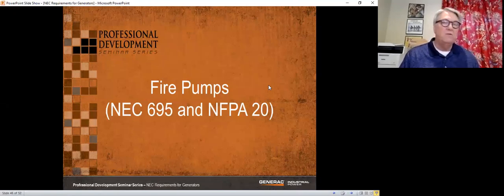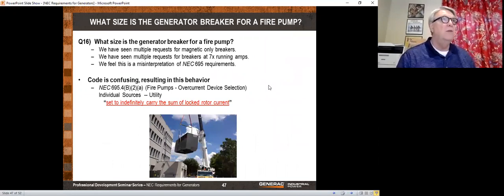And our final thing is fire pumps. I've always said that the way they wrote the section on fire pumps is they promised a free cruise to anyone who could write an entire section of code that absolutely no one could understand. And so we could talk for a complete hour just about fire pumps. So let me just give you a couple of the highlights. If you have a circuit breaker on the utility that feeds the fire pump, it must be set to indefinitely carry the sum of locked rotor current. In other words, it's a fire. They're never going to trip the motor. They'd rather let the motor, the fire pump, burn up than trip it.